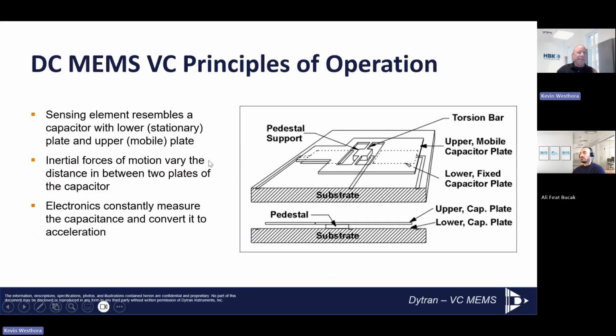But this is the technology of a variable capacitance DC MEMS accelerometer. There are three ways to measure acceleration in the industry. You can measure it with variable capacitance technology, which is what we're talking about today. You can use piezo-resistive technology, which is a strain gauge based technology, used for two applications: high shock and crash testing in automotive. Those applications use piezoresistive because it's a high-G application.